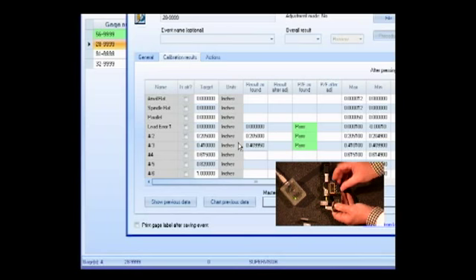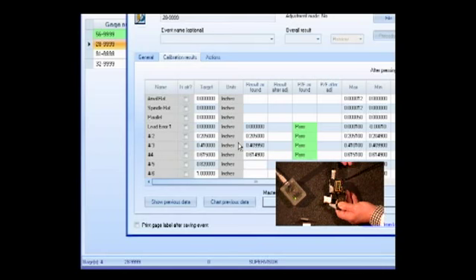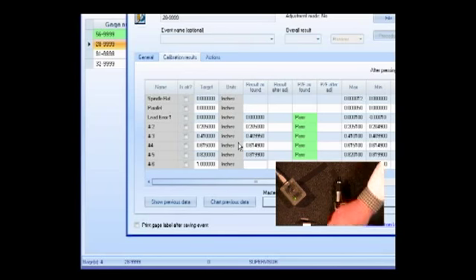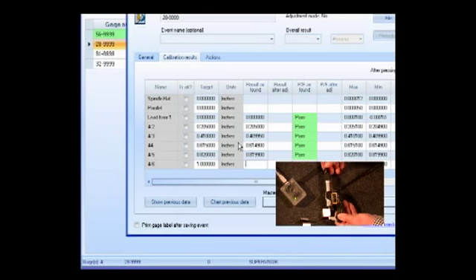Now, up at 615, our checkpoint, it actually measures a tenth low. It measures 614.9. It's still in tolerance, but you can really see the wear. And this is a good example for our viewers to know when you use the tool at the same place over and over and over, it will wear. It may not wear much, and some will say, well, that's not a lot of wear, but that's the tolerance of the gauge. And that's because this is being used at the same range all the time. Right, repeatedly for a certain type of measurement. And what happens, the lead screw or whatever starts to wear? It's a number of factors. Okay. Sometimes the faces wear. That would show up in the flatness or the parallel, sometimes the lead screw. Okay. Again, at 820, it was still worn to the tolerance, but still in.